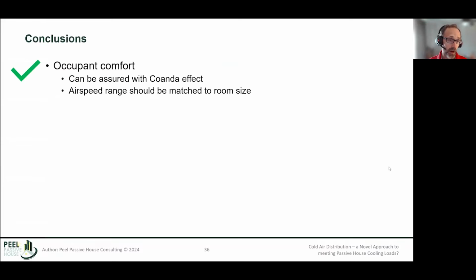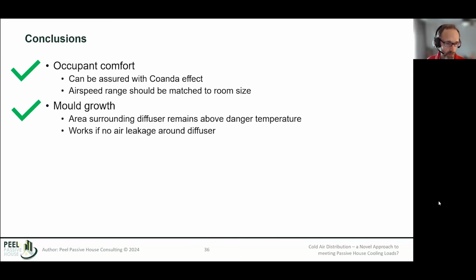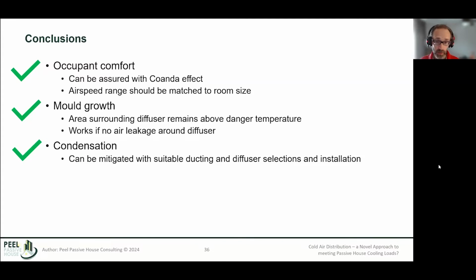So just a little summary here. The three risks we looked at: occupant comfort. Well, we've confirmed that using the Coanda effect, we can ensure occupant comfort even at these really cold delivery temperatures. We do want to make sure we match the airspeed range coming out of the diffuser to the room size. Mold growth: with the right diffuser selection and positioning, that is a risk we can mitigate, in particular dealing with air leakage around the diffuser. And condensation: provided we choose the right kind of diffuser, install it correctly, and also install ducting correctly, we can mitigate that. I'll come back to the ducting side of things in a bit.